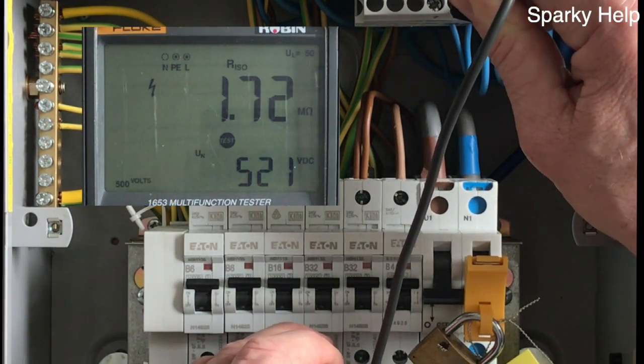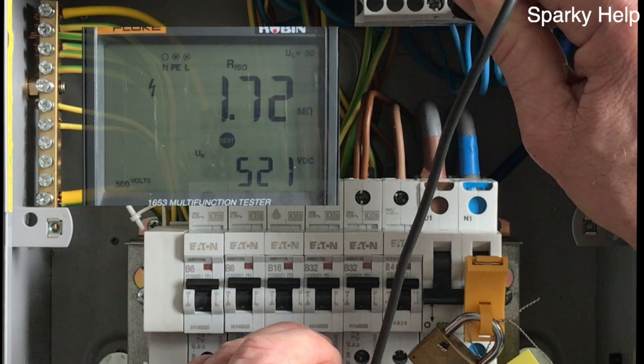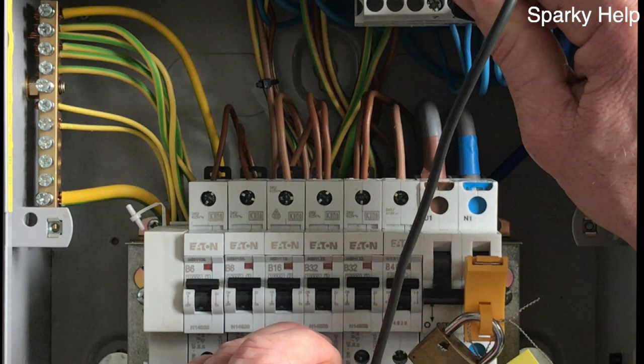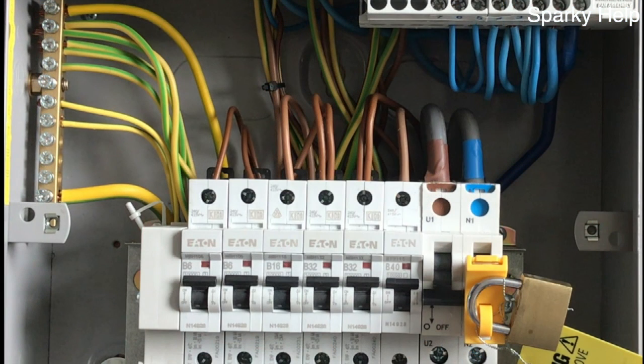So we've got 1.72 megaohms. Not a fail, but you might want to investigate that. As we're testing a group of circuits, further investigation requires us to find out which circuit may be at fault here. How do we find it?